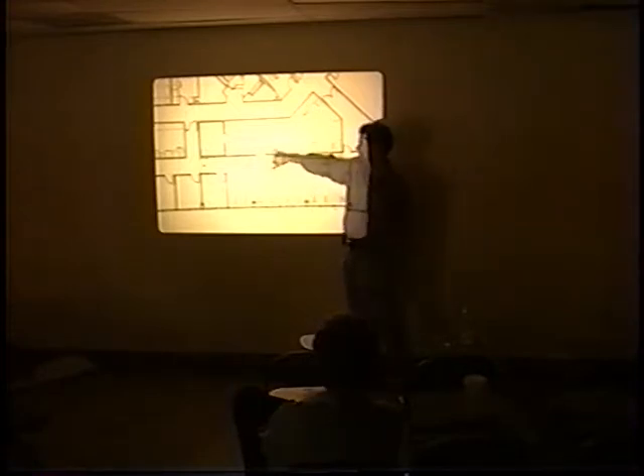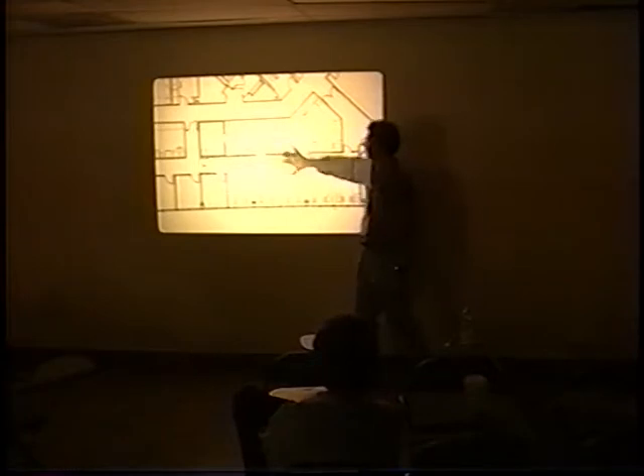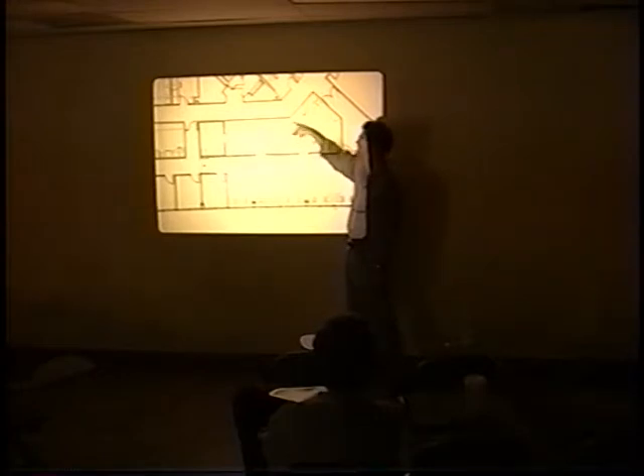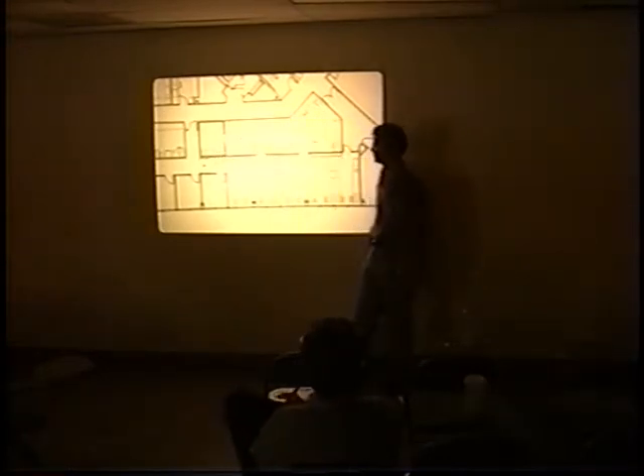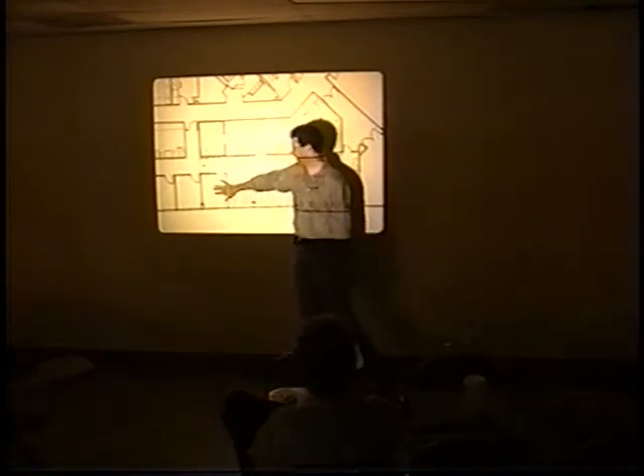The noisy things, like centrifuges that spin up to, say, 10,000 RPMs, need to be put into the secondary suite, which is almost a generic open space that will allow for plenty of lab bench space, workspace, centrifuge space, fume hoods, and a pharmaceutical cold room. This is a whole ice box that's refrigerated down to, say, 34 degrees or so. And that actually is chilled by something on the roof, and it's quite interesting.